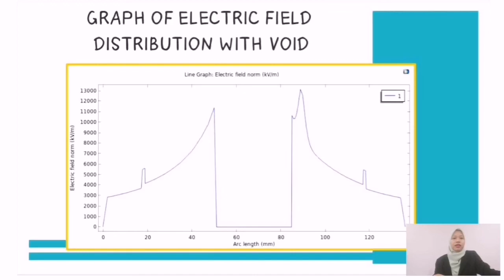When the void is present in the insulation, the electric field of the void is increased as shown in that figure. The electric field at the void is higher due to the lower permittivity than the insulation material, so the insulation material has to withstand more stress at the location of the void. The breakdown strength of the void, which is air, is lower than the insulation material. So, the breakdown strength of the insulation material is decreased due to the void inside it.